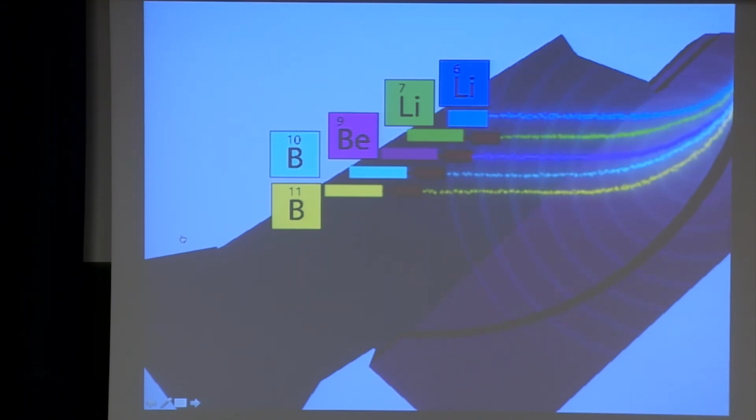It's a normal mass spec. An ion that flies through a magnetic field feels a force, and it turns. The heavier ion is more difficult to turn than a light ion, and that's why they come out of this magnet sorted according to their mass, grosso modo. In this machine there are 5 detectors. From the same small spot on the sample, you can pick up 5 different ions.